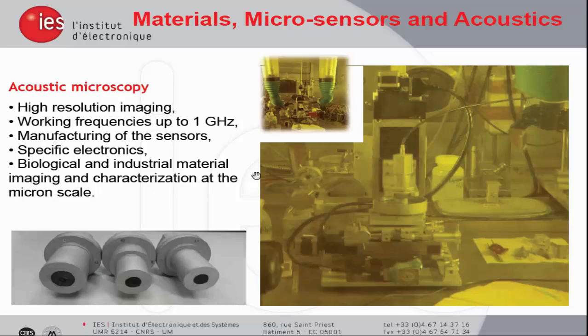An acoustic microscope is a high-resolution imaging device that works at frequencies up to the gigahertz to allow resolutions down to the micron or less. And we manufacture our specific acoustic sensors and the electronics to allow the imaging of industrial and biomedical applications. Here you've got an image of our sensors and of an acoustic microscope that we introduced into a European joint laboratory, next to a nuclear hot cell. It was designed to perform images of nuclear fuel after combustion.